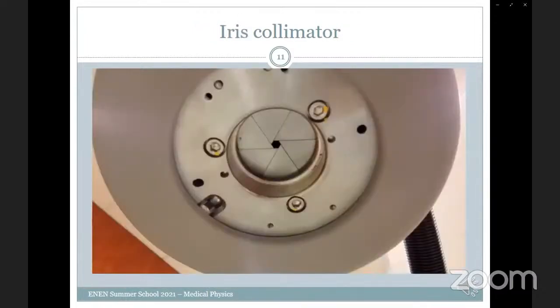With the iris collimator, they made some upgrade of this collimator type, because the iris collimator can create the same field sizes from 5 mm up to 6 cm, but it can change the field size automatically, so you don't have to enter the room for changing field size. But still, the field shapes are only circle shapes, so still you cannot do intensity modulated radiotherapy.